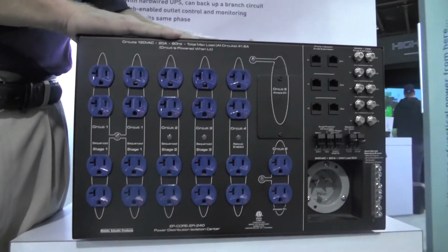Instead of bringing 3 or 4 dedicated 20 amp circuits to where the rack is going to be, we're going to provide a 240 or 208 volt feed. This then plugs in, and now I have 6 20 amp branch circuits here in the rack mount version. This will isolate all of the AV equipment away from everything else going on in the house.